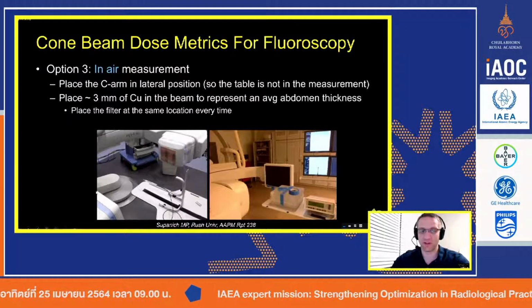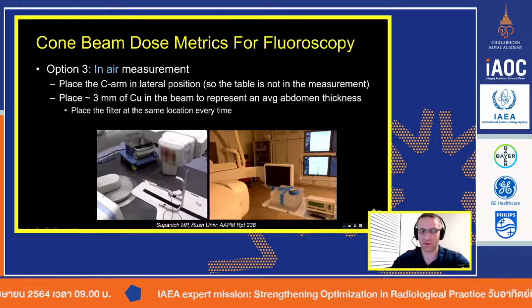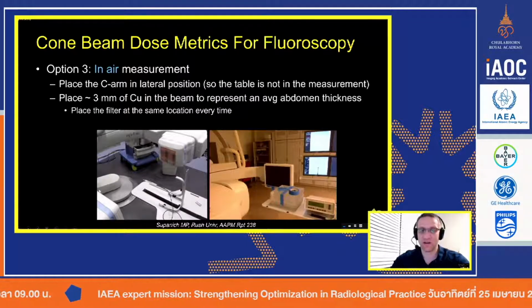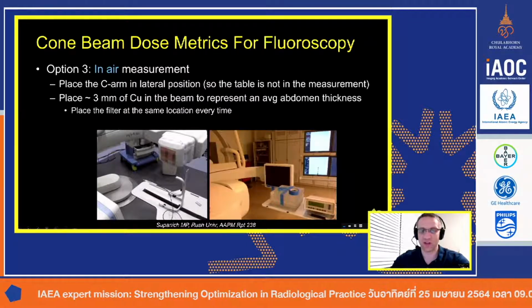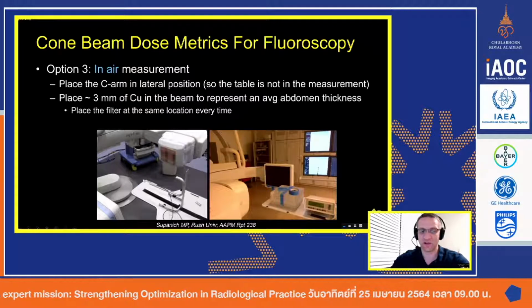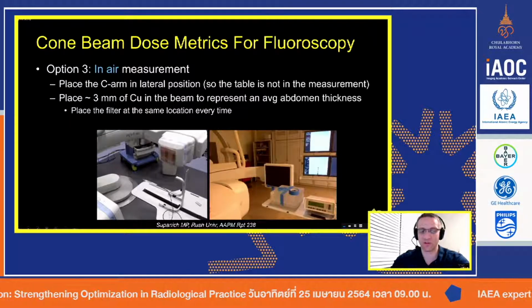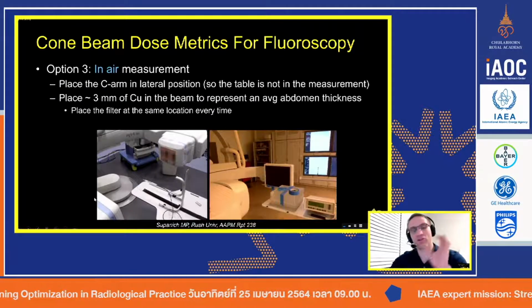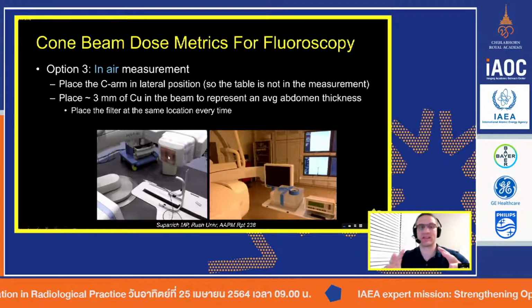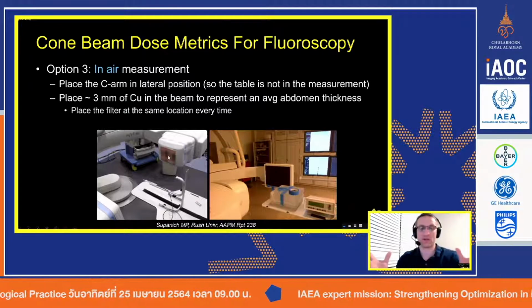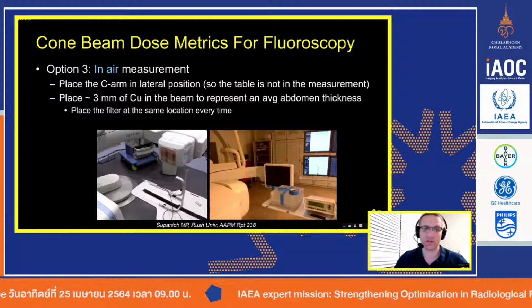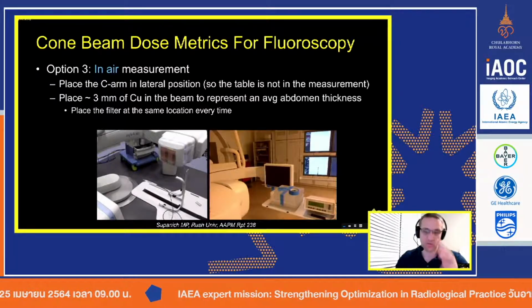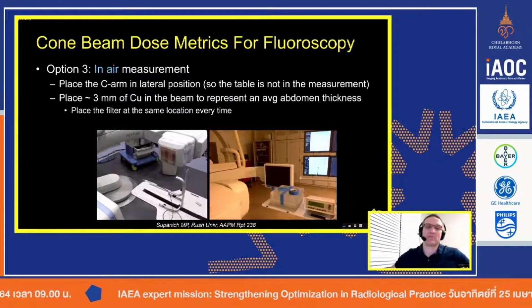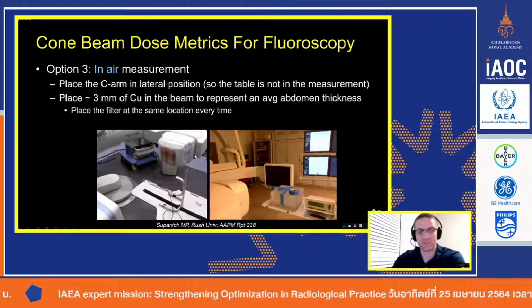If you put the copper filters on the detector side, then the photons will not attenuate, so the value will be high at your ion chamber, but then they will be low at the detector. It doesn't matter. You're using that copper to make the system think there's a human being on that table. 3 millimeters of copper is a roughly good way to approximate the abdominal thickness of an average human.